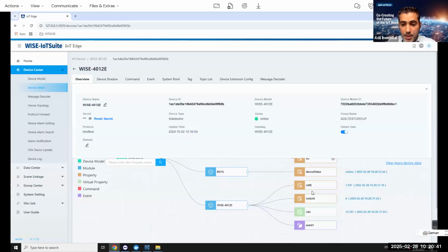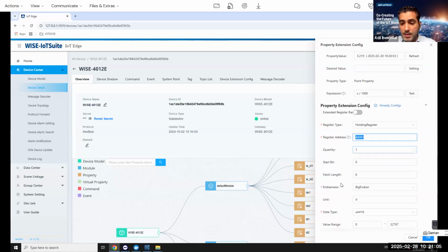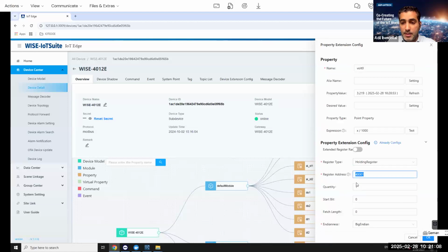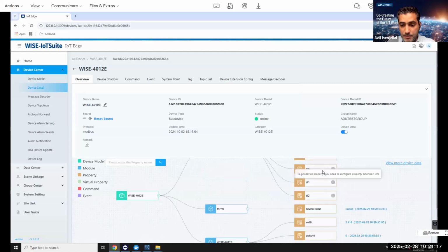So here, one last thing in the flow. Because I'm using Modbus, it needs Modbus registers information. So here when I click on it, as I said, it's a little bit similar to Node-RED. So for people who are familiar with Node-RED, it's really easy to handle. And here I'm using this Modbus address. Here I did this kind of scaling to get exactly the value I have in the utility. Here you see we have the analog inputs and the relay status.